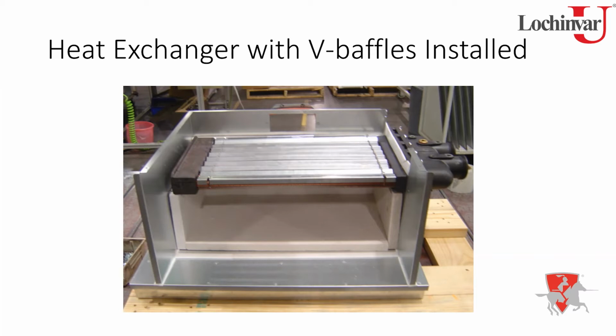But also, if there's a lot of soot buildup on those fins and you hit that with a wire wheel and create a spark, it will actually catch on fire. You will start a combustion process at that point with that carbon. So you don't want to do that. Always just use that stiff bristle brush. Absolutely. And this is something that we're asking you to do annually. So once a year, we are looking for this heat exchanger to be cleaned up. One thing to keep in mind, if for some reason you get in here and it's very sooted up and very blocked on all these copper fin tubes, you may in fact have to remove the heat exchanger from the combustion chamber itself.